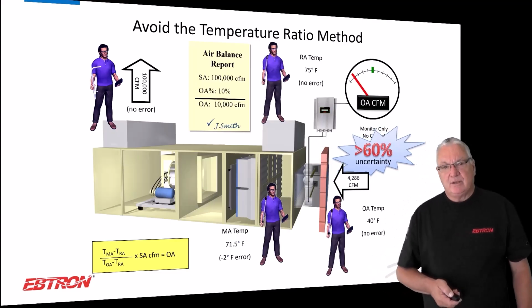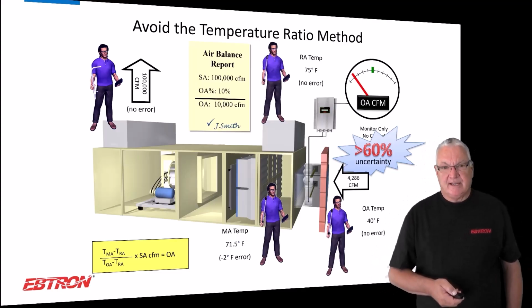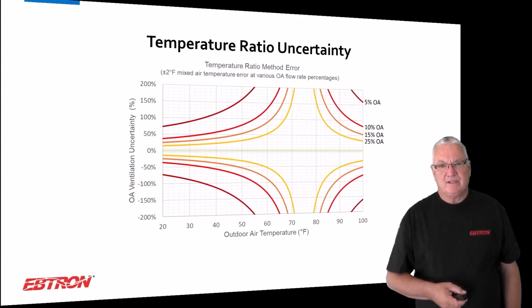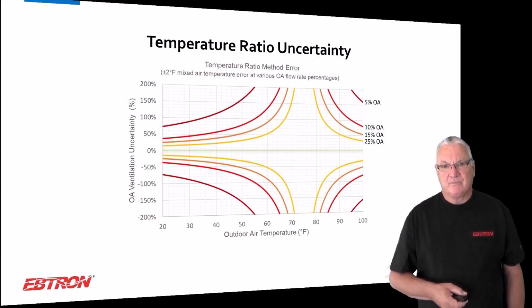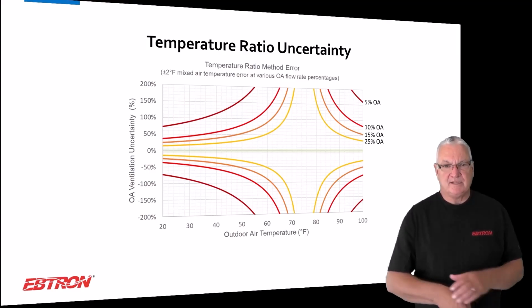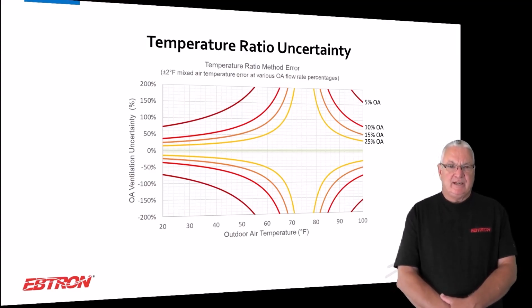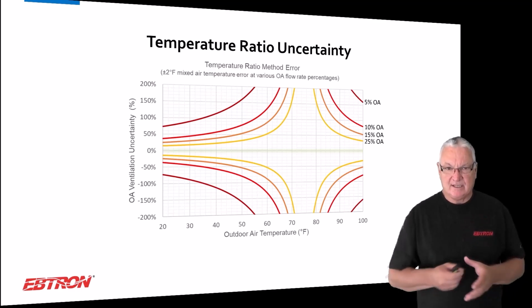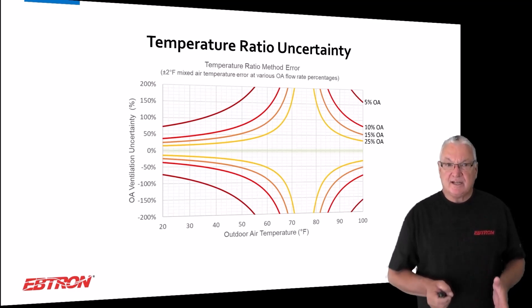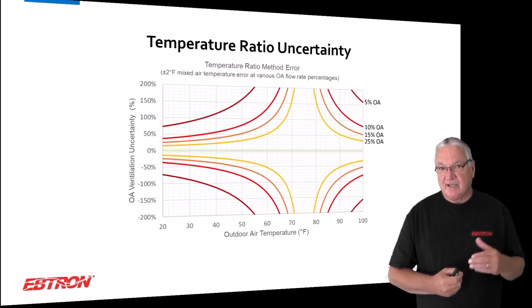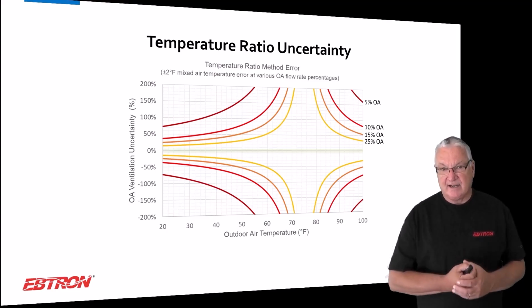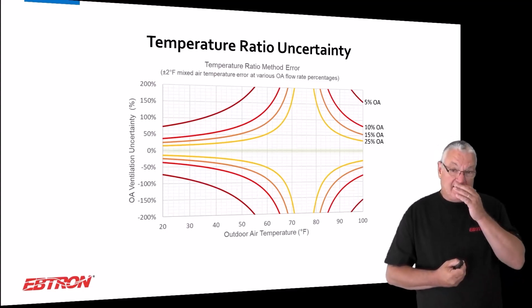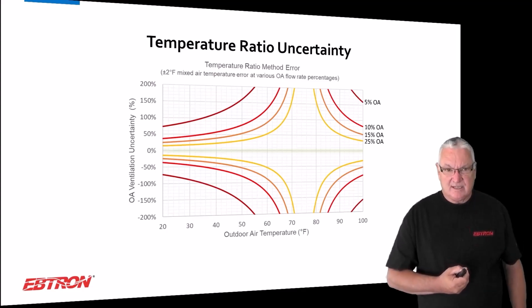And so you say, well, Dave, you probably picked some crazy example. And I was like, no, let me carry this through to a more broad example. I said, look, I'm going to keep the 2 degree uncertainty of the mixed air the same throughout this, with no other errors, just like on the previous slide. And I'm going to look at different percentages of outside air into supply air, or mixed air, running from 5 to 25%. And when I take a look at this, the errors are huge.